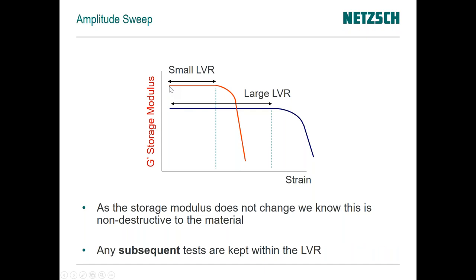If we characterize the stretching of a rubber band or a spring with weights, we can identify where the material performs linearly for each applied load versus when the material starts to break down and fail. For something like mayonnaise or yogurt you'd see a plateau region where the material isn't changing as a function of amplitude, until we reach an amplitude where the structure starts to completely break down. Our goal is to test materials in this linear region because it's very reproducible and tells you about the state of the material.